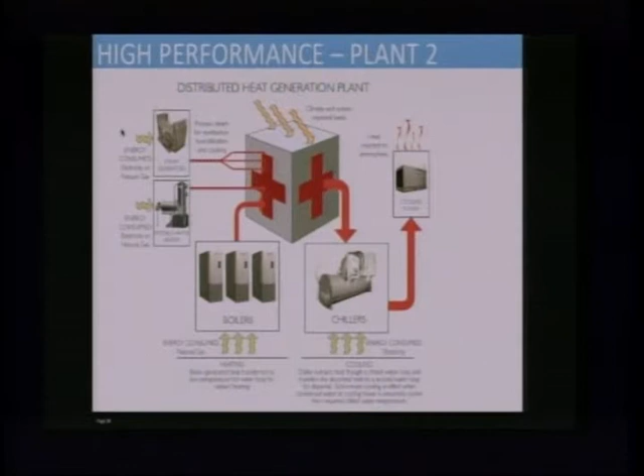As an example, the boilers are serving the reheat loop. Then there are point of use steam generators, and there's domestic hot water. All of those needs are heat at different temperatures, and so the equipment can work at its most energy efficient mode to develop the heat at the right grade.